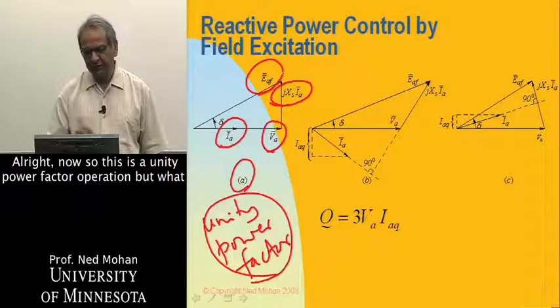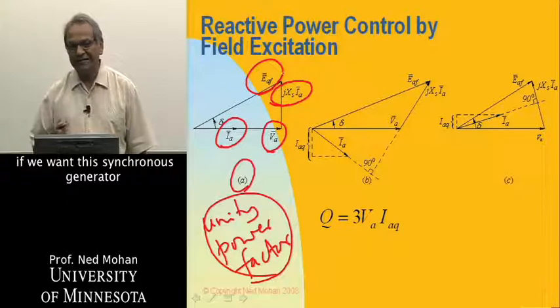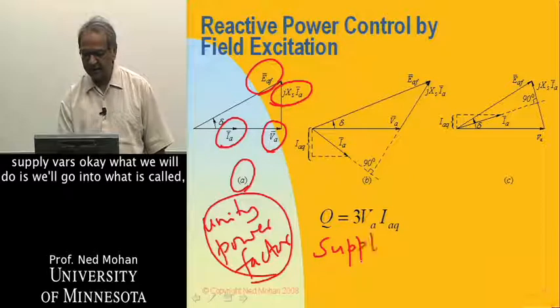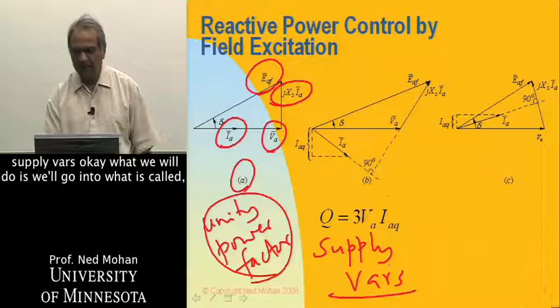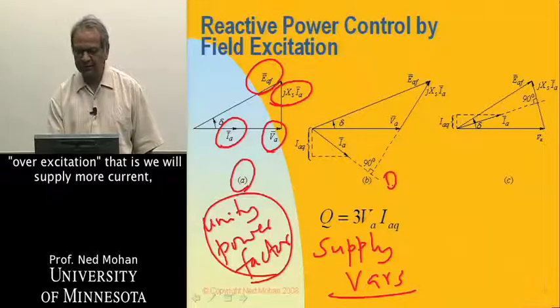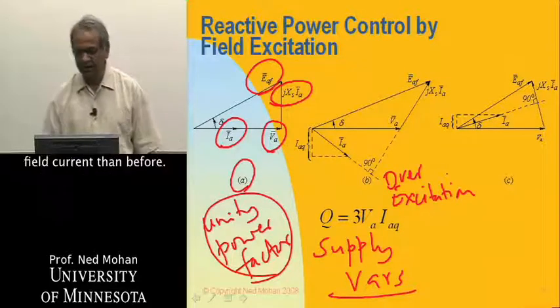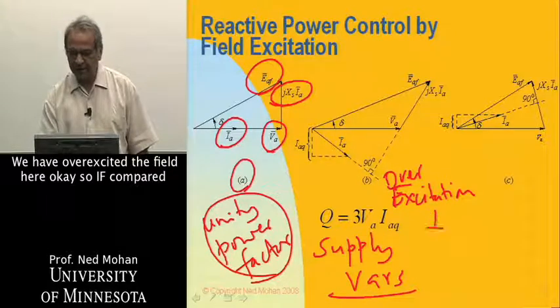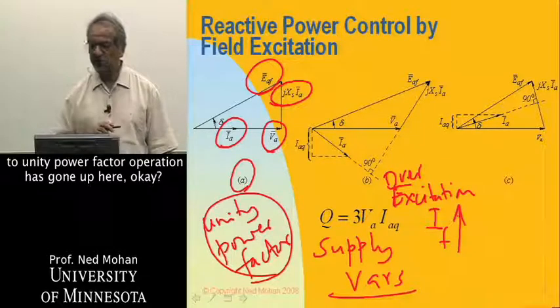This is unity power factor operation. But what if we want this synchronous generator to supply reactive power — supply VARs? What we will do is go into what is called over-excitation. We will supply more field current than before, over-exciting the field. So IF compared to unity power factor operation has gone up.